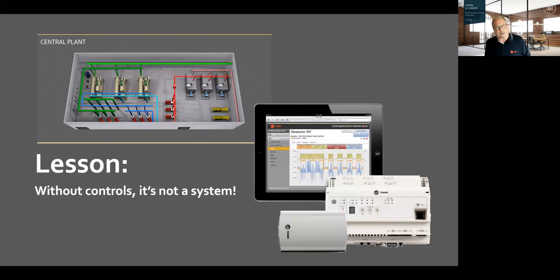So, the lesson we've learned, many of us, I'm sure, have also learned out there, is that without controls, it's not a system. A lot of this information needs to be centralized. It doesn't matter whose system it is. If you have chiller plant controls, I'd advise you to use somebody that knows chiller plants. That kind of goes by geography. Different manufacturers or vendors are better at chiller plants than others, depending on the area. But regardless, you might have 2 or 3 systems out there, but BACnet these days is a protocol that will allow you to poll all those chilled water valves, for instance, and determine how fast that pump should go, and whether or not you have a couple of bad coils out there that could be, again, driving that chilled water pump to run at full speed.